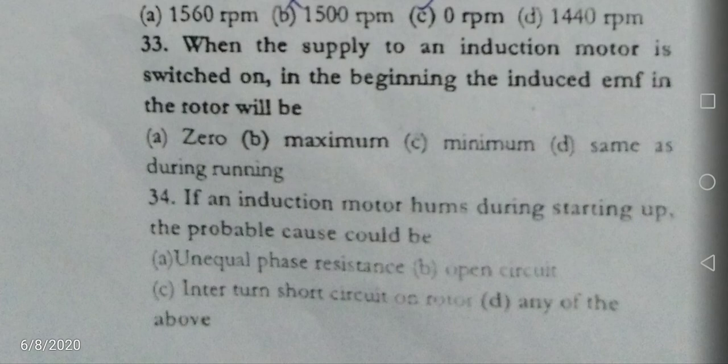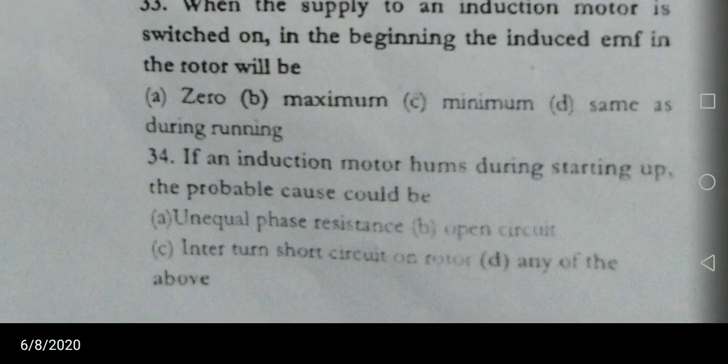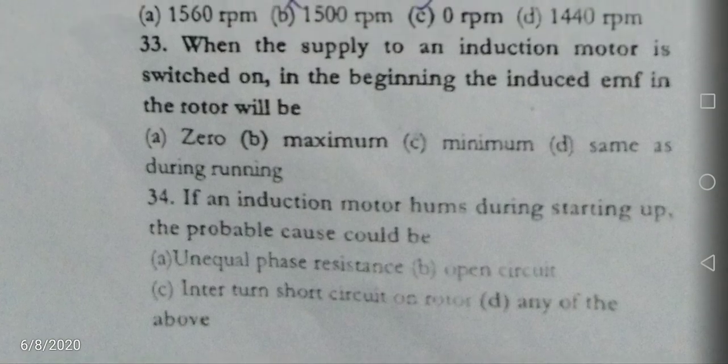If it is open circuited, humming noise comes; with unequal phase resistance also, and with an interturn short circuit on the rotor. So all three are correct, so any of the above; in that condition the machine will hum.